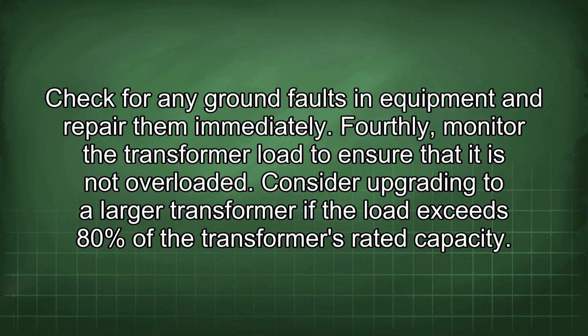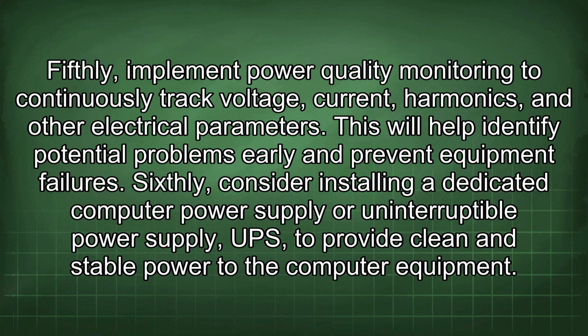Fourthly, monitor the transformer load to ensure that it is not overloaded. Consider upgrading to a larger transformer if the load exceeds 80% of the transformer's rated capacity. Fifthly, implement power quality monitoring to continuously track voltage, current, harmonics, and other electrical parameters. This will help identify potential problems early and prevent equipment failures.